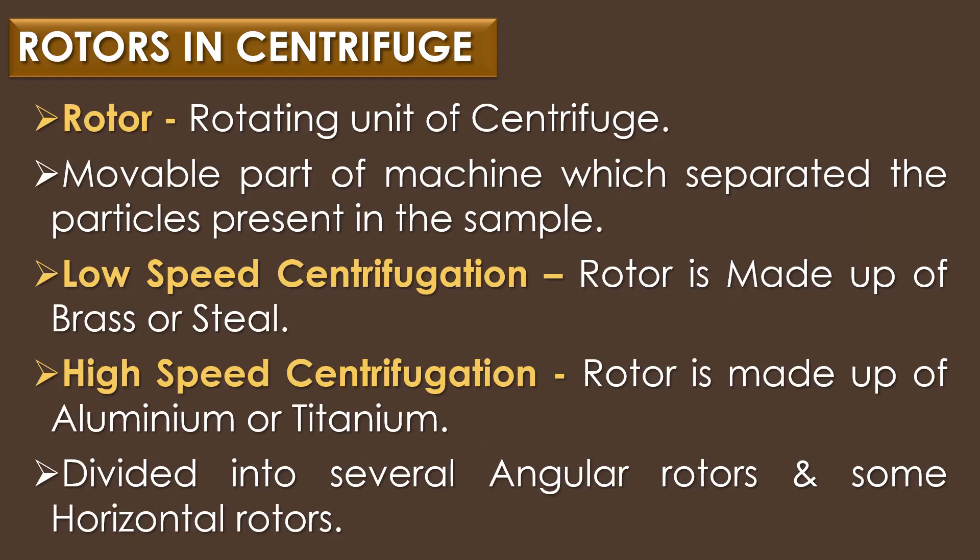Rotors. The tubes or bottles containing the liquids to be centrifuged are held in place by the rotor. The rotor is the rotating unit of a centrifuge and the movable part of the machine which separates the particles present in the sample. For low speed centrifugation, the rotor is made up of brass or steel, and for high speed centrifugation, the rotor is made up of aluminium or titanium.